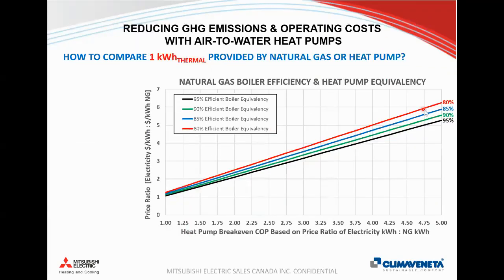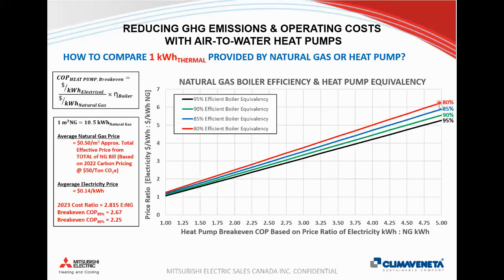And when we plot this equation, it's pre-plotted here for different efficiencies, so 95% in black, as low as 80% here in red. So what we do is we figure out what our price ratio is, and I'm on the condo board for my building, and I've been looking closely at our utility bills over the last couple of years. In December of 2022, our average delivered rate for natural gas was about 50 cents, and our average delivered electricity price was about 13 cents. So I'm using 14 cents here to be a little bit more conservative. So essentially, you figure out what your cost ratio is when you convert these into kilowatt hours. So the 2023 cost ratio is about 2.815.